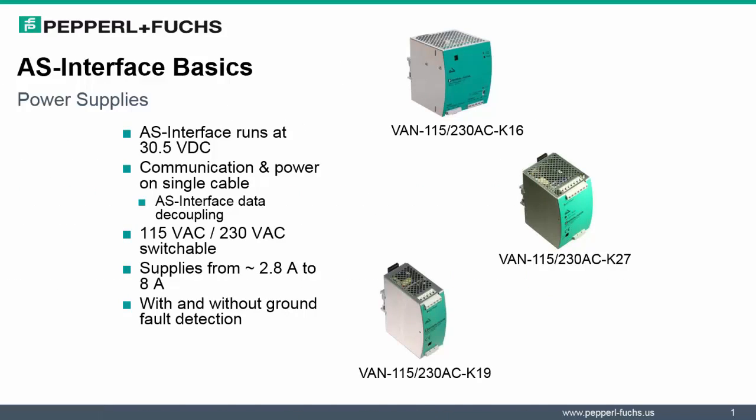AS Interface power supplies are very important in the network. These power supplies are unique because they have data decoupling built in them. Data decoupling is a very important aspect of an AS Interface power supply because communication and power now could be transferred on the single cable. The maximum current capacity of AS Interface power supplies ranges from 2.8 amps to 8 amps. AS Interface power supplies have a really nice feature in that they have short circuit and overload protection when limits are exceeded.